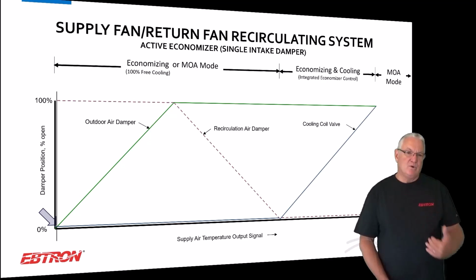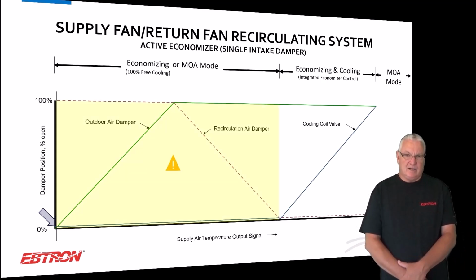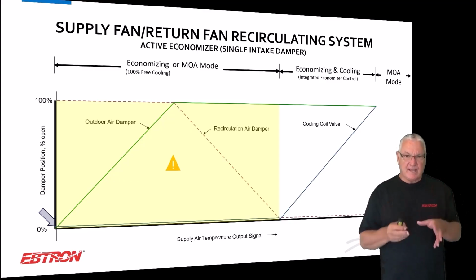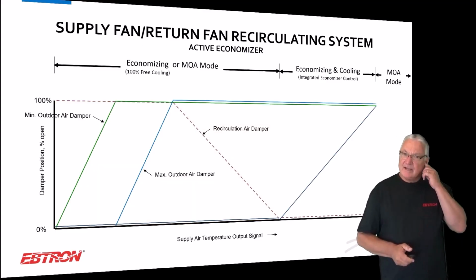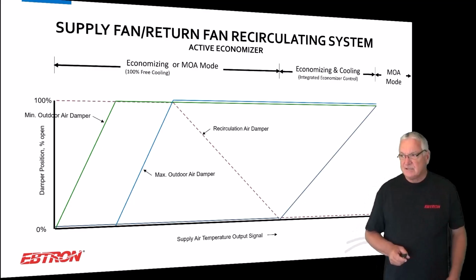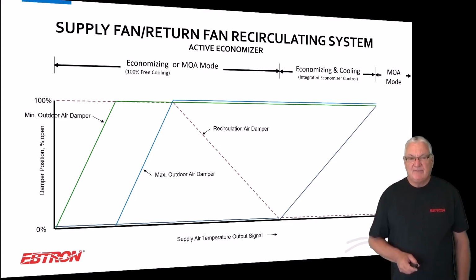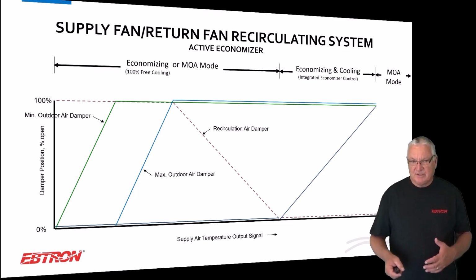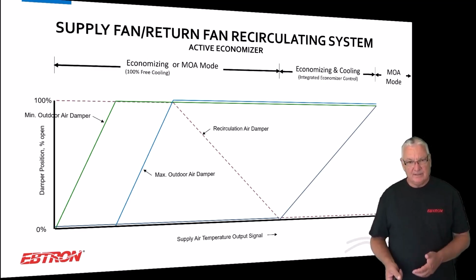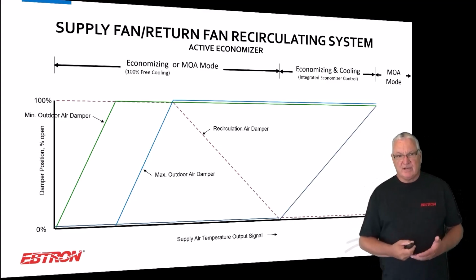Okay, so I mean, you really wouldn't go all the way fully shut. And I caution people in this area just to look at it and make sure you understand that about your measurements and your velocities and things like that. Okay, now when you do min-max, this is opinion. When you do min-max, you have a decision to make. When I'm in economizer, do I want to control the max and min dampers together? Do I want to control the min damper first or the max damper first as I'm reducing my outdoor air? And to me, it's pretty straightforward.